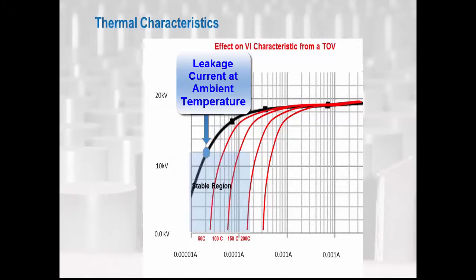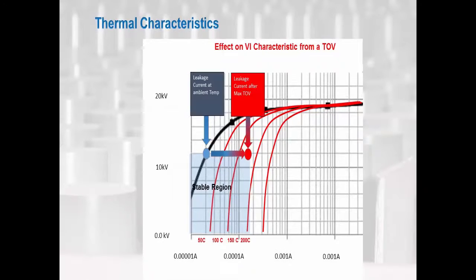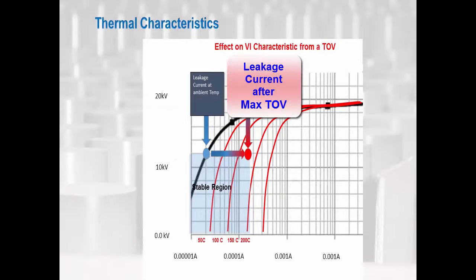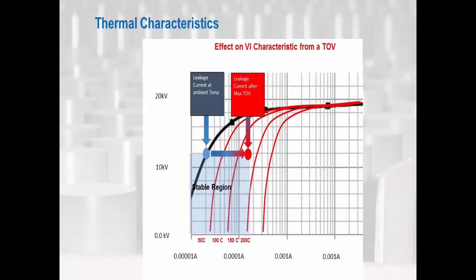The leakage current of an arrestor is quite low at normal operating temperatures. However, if the temperature of the disc increases from an operation, the leakage current will also increase. It is shown as the blue dot on this graph. On this second graphic, we can see how the temperature increases after a surge or TOV event. In some cases, its temperature will rise to near the maximum stability limit of the unit. This is how the arrestor power frequency over voltage capability curve, or TOV curve as it is better known, is determined. Energy is injected into an arrestor and then it is checked to see if it will remain stable.